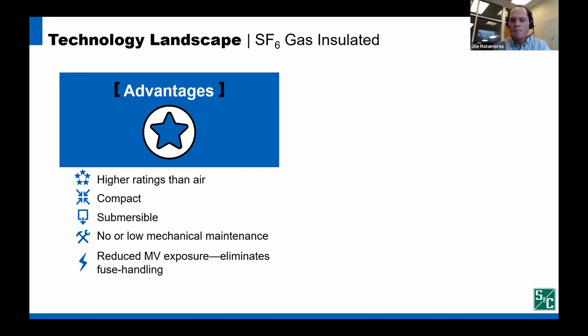Gas insulated gear typically uses resettable fault interrupters instead of fuses. Gas insulated gear allows us to further reduce crew exposure to medium voltage by not using fuses. Lastly, gas insulated gear typically includes three position switches. These switches provide both a visible break that can provide a clearance, and they provide a way to ground cables without removing, parking, and grounding heavy cables.